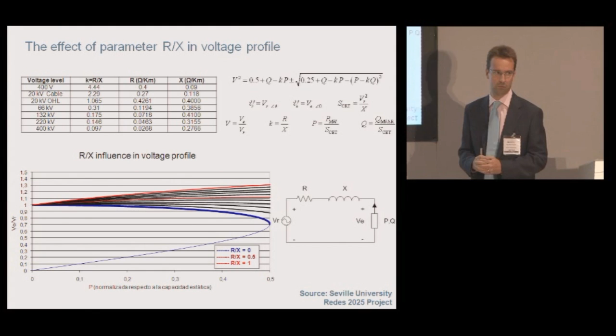And what we've seen is that, due to the resistive-reactive parameter, which is very low at high voltage grid, when we are injecting active power in the grid, active power is becoming a very significant driver for voltage changes. And active power is not significant when we are considering high voltage. In transmission and in distribution in the high voltage part of the grid, the active power injection is not very significant in terms of voltage control.